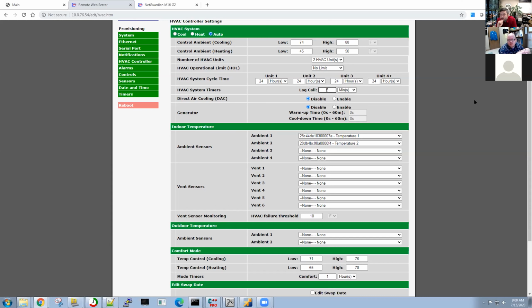And yes, lag, but we're only talking about 2 units here. We'll add extra visibility into that too—I think if we get into that no-momentum-detected state, it generates one of those system alarms and can send a notification out. So if HVACs are on but aren't making enough progress toward the endpoint for that configuration, we can notify out that we've got HVACs running but it doesn't look like we're going to complete the job with the horsepower we've got running right now.